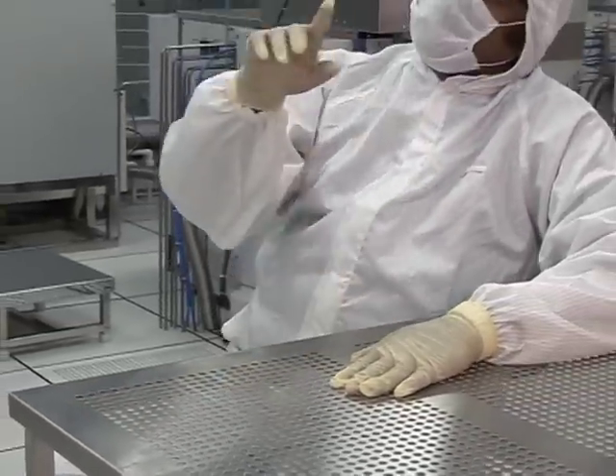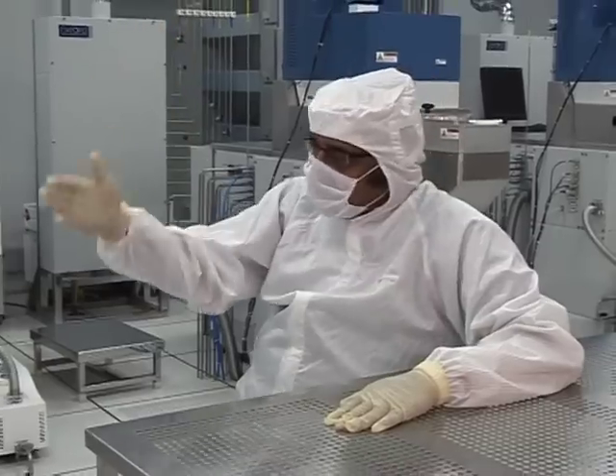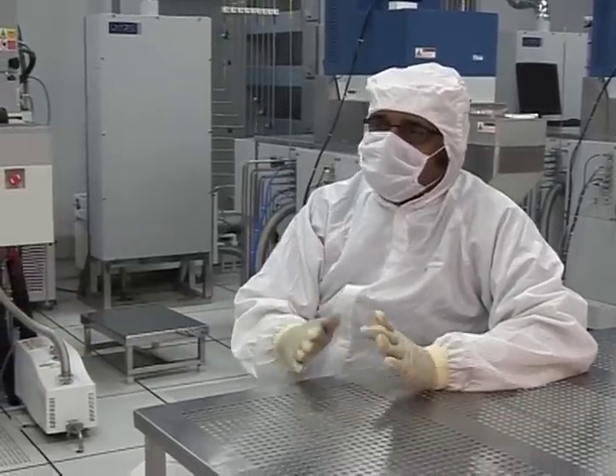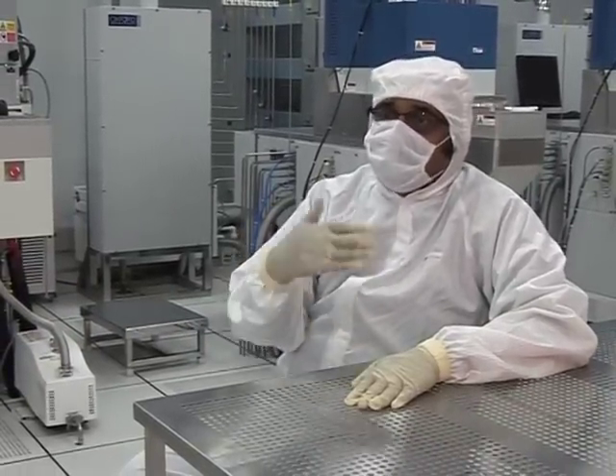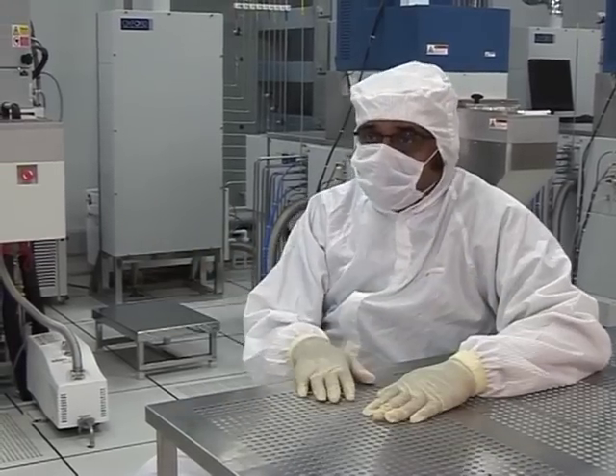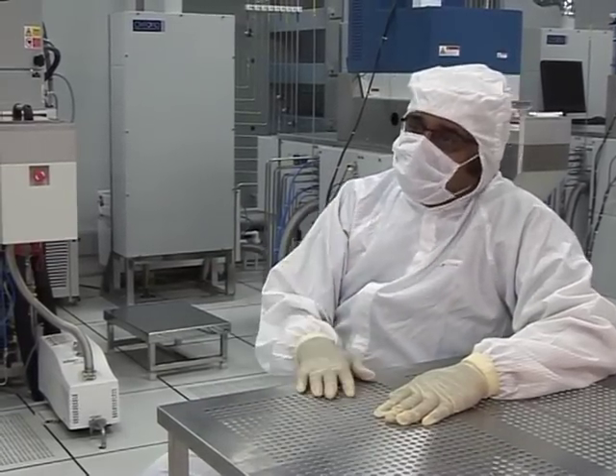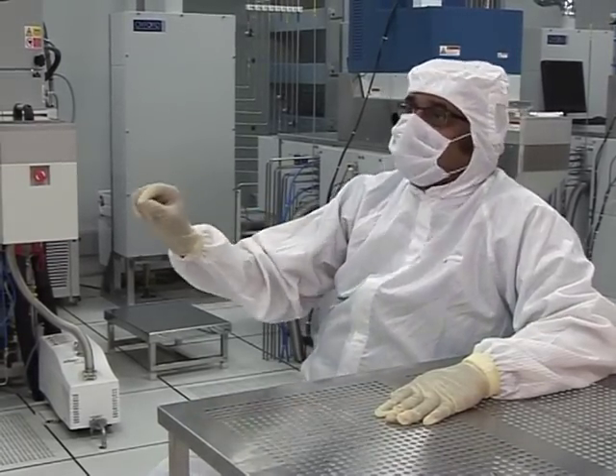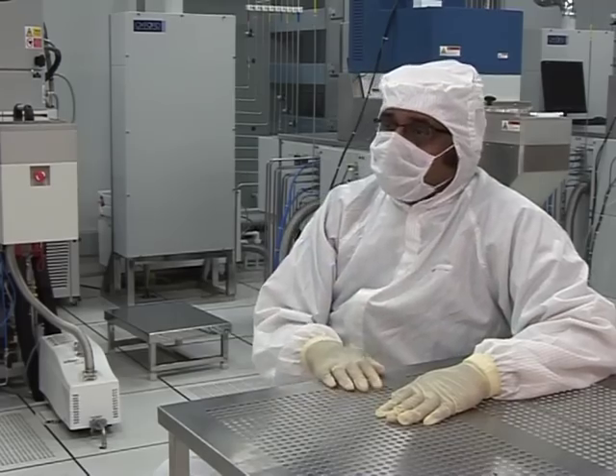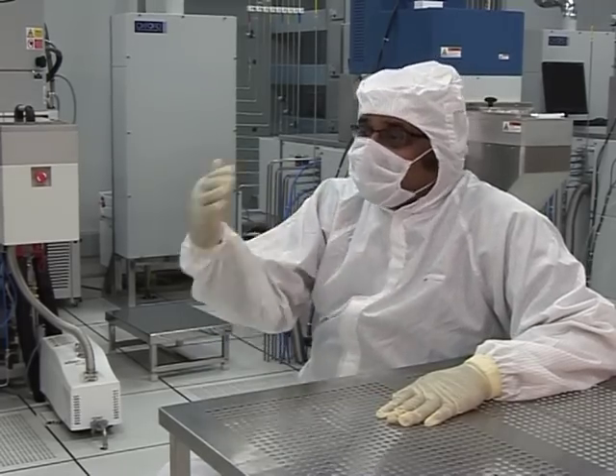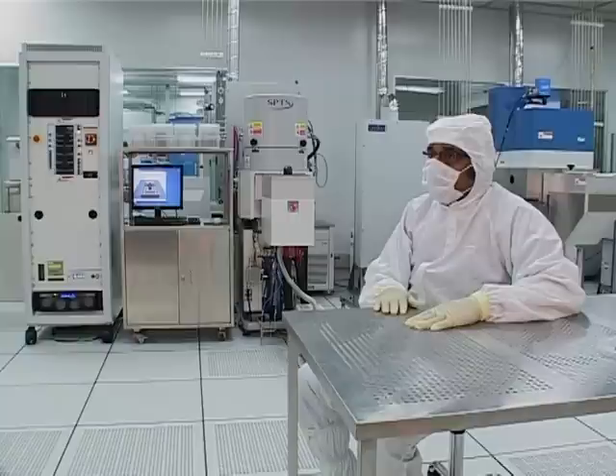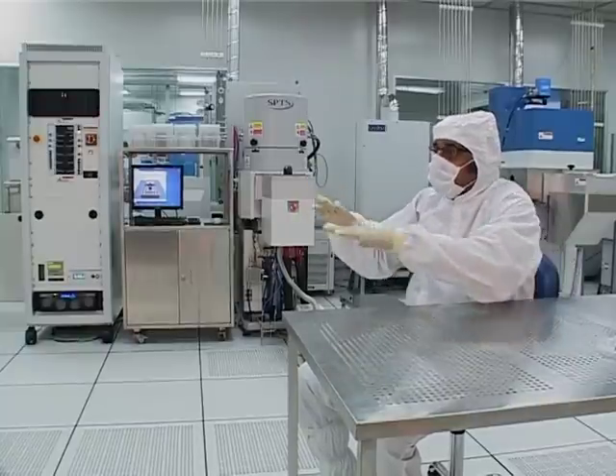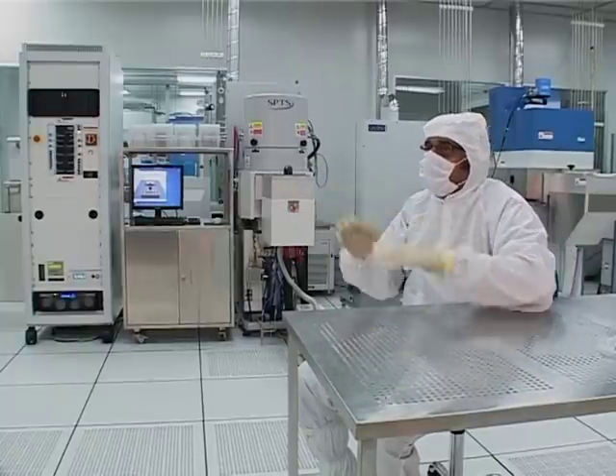And also here, the number of fan filter units and the number of perforated tiles are designed in such a way as to maintain a class 1000 condition in this clean room. And also the design is such that there is no area where there is stagnant air. That means if there is stagnant air, the dust gets accumulated in that area. So we should always make sure that the entire area has got moving air.